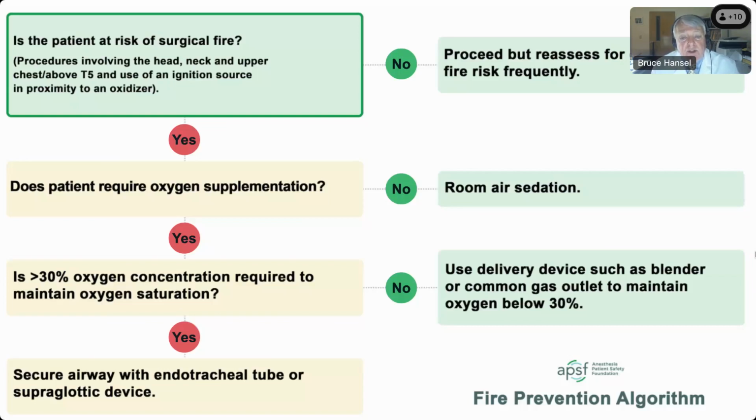And that's another engineering solution that I think is near and dear to Dr. Feldman's heart: use of O2 blenders, having them available in all anesthesia settings so that you have an easy way to control auxiliary oxygen, because a lot of these fires involve auxiliary oxygen, not oxygen from, as mentioned earlier, the common gas outlet from the machine, where you'd get anesthesia vapors as if you were delivering an inhalation anesthetic via tube.